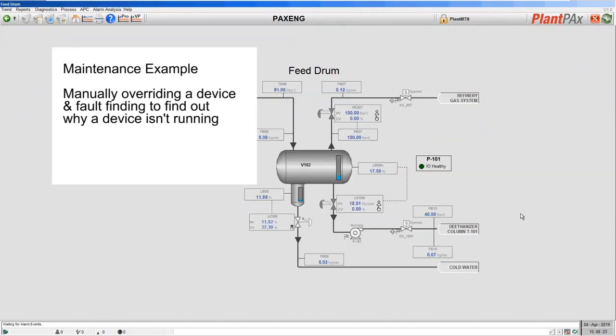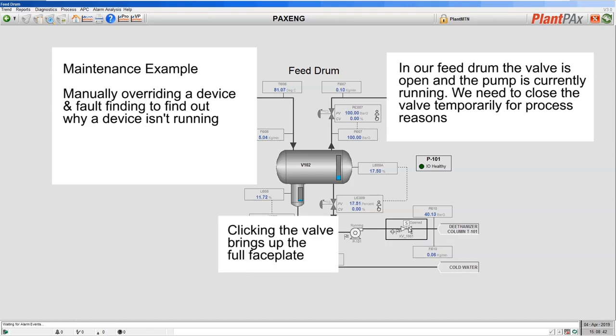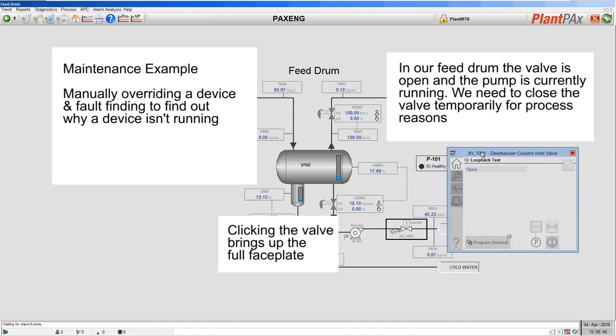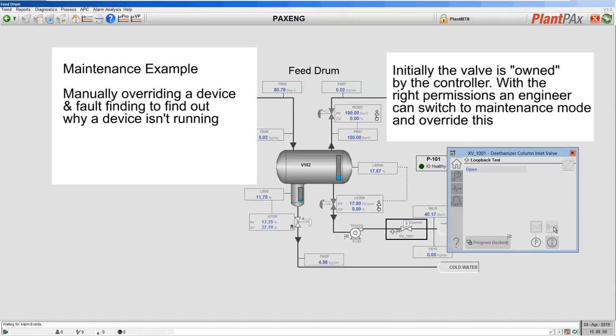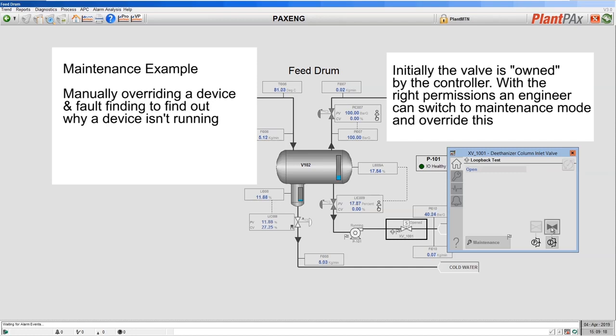In our final example, let's show overriding a device and using the diagnostic capabilities built into the library to determine why a device is not running. In our feed drum the pump is running and the valve is open, but let's say there's a reason I need to close this valve. I bring up the full faceplate — at the moment I cannot close this valve because the device is being controlled and owned by the controller, but using standard features in the library I can override this. The first thing I need to do is put the device into maintenance so that I can override its current commanded state, so from the faceplate I will request maintenance control.